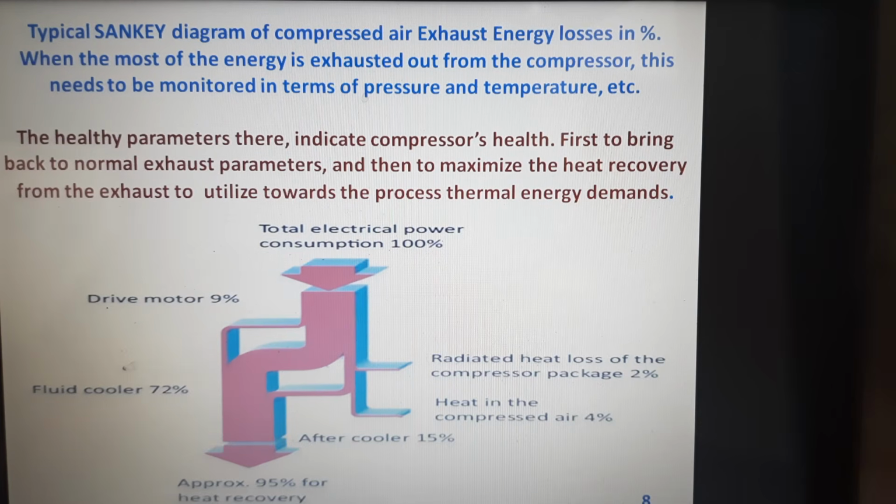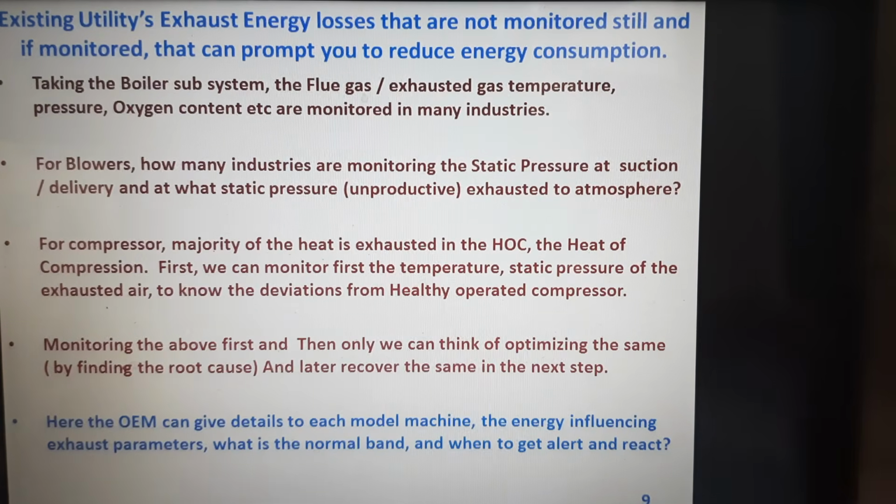Once it is monitored in temperature and the static pressure, you can also check with the compressor OEM what the norms are and where we are maintaining it as such. It is a band, we have to maintain it.